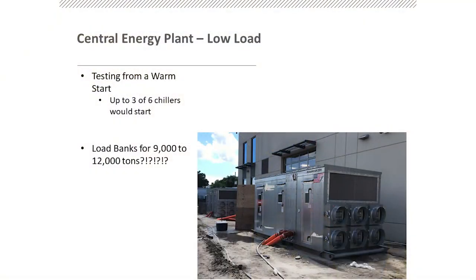The image on the right-hand side is a project that we had done at a much smaller chiller plant. It was only 800 tons installed. Same concept: it was built for a campus where the campus buildings were also being built, and miraculously the chiller plant was available before them. We were able to get some air handling units and falsify that load through the emergency chiller connection, and dial it up and dial it down to see the chillers stage up and stage down. But are you really going to do that with 9,000 tons? Pulling up some boilers and connecting them in is not really feasible. It wasn't in the budget, so we had to put our heads together.